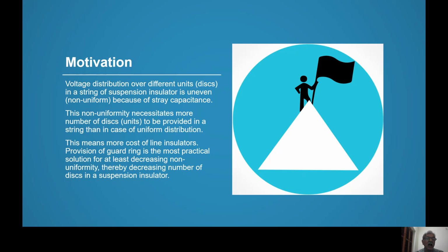And another is the guard ring. Guard ring is the cheapest solution and the easiest solution, technically the most feasible solution. It does not give exact uniformity, but more or less nearer to uniformity it will give. Therefore, people use guard ring. You might have seen that there is a ring near the high voltage, a ring connected to the high voltage conductor. That ring is trying to equalize the voltage across the different suspension insulators.